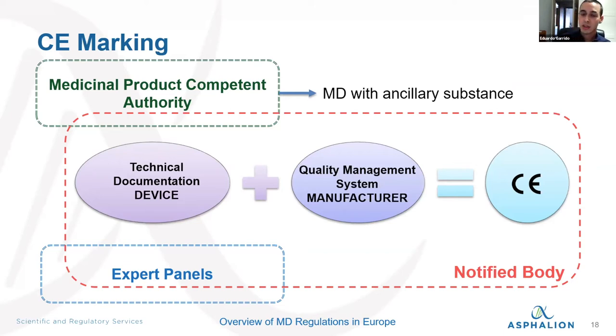Once you have these two things, you can undergo CE marking, and there are some entities that may or may not participate, depending on your device, in the CE marking process. The first is the notified body — if your device is higher than class one, you will require a notified body; if not, you don't need it. Then there are medicinal product competent authorities, which get involved in products that incorporate a medicinal product as an ancillary substance. And there are also expert panels that will be assessing certain kinds of products.